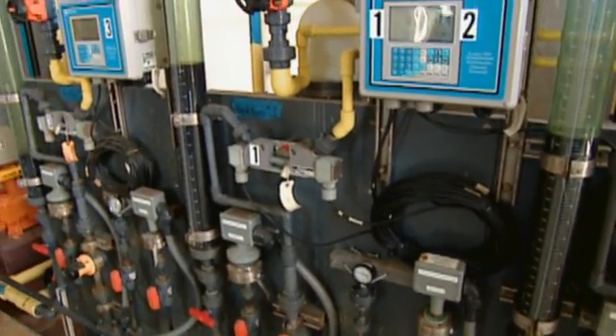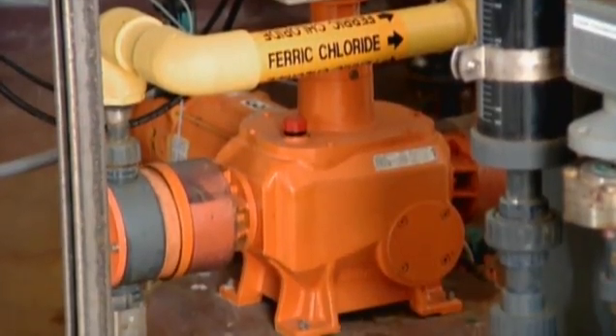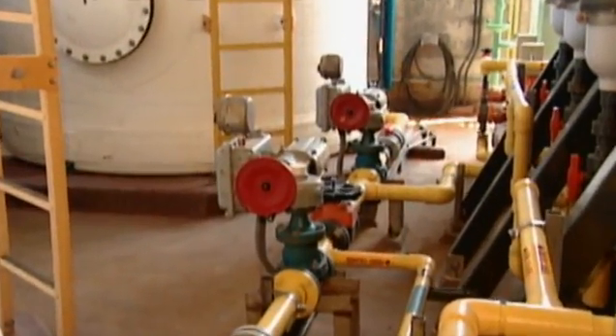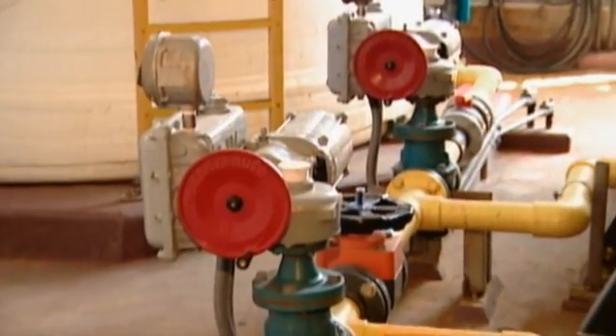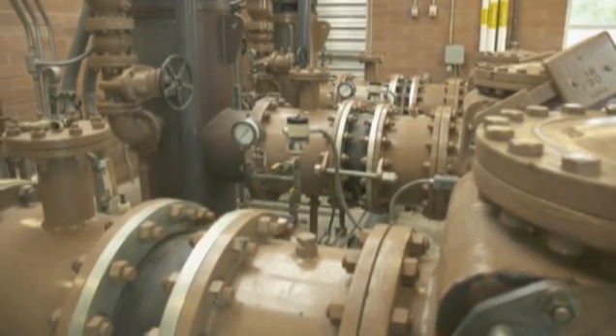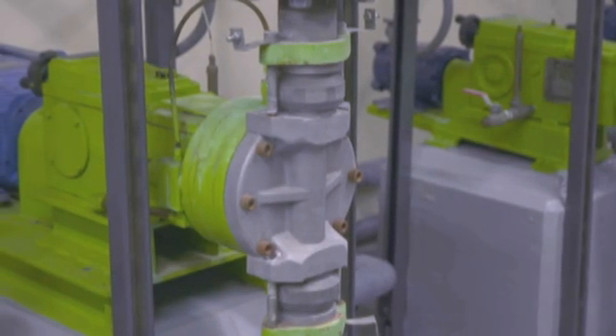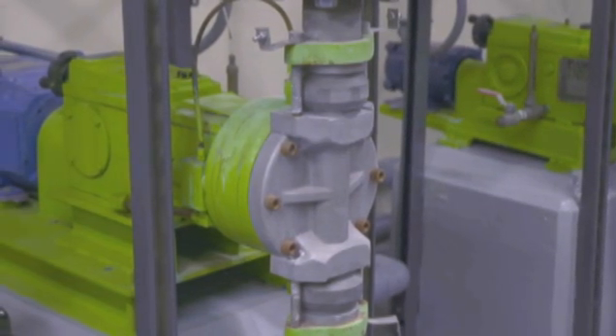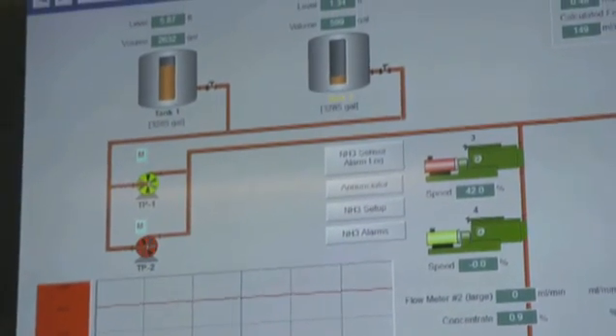Positive displacement pumps displace or move a uniform amount of fluid each cycle or revolution. Generally, they have two cavities: an opening or expanding area that creates suction and draws liquid in, and a closing or decreasing area that pushes the liquid along. PD pumps produce the same flow at a given speed no matter the discharge pressure, and are often used as metering pumps.